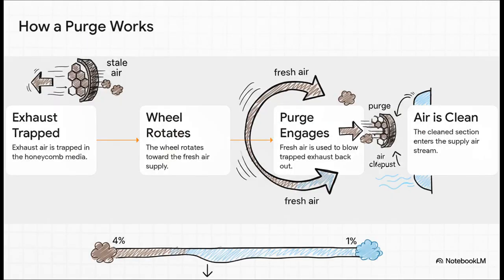As the wheel rotates out of the exhaust stream, it's got stale air trapped inside its honeycomb media. Now, just before that section enters the fresh air supply, the purge plate diverts a little bit of clean air backwards through the wheel, blowing out or purging that trapped exhaust. This one simple action can knock contamination down from around 4% to just 1%. That's how you keep the air clean.